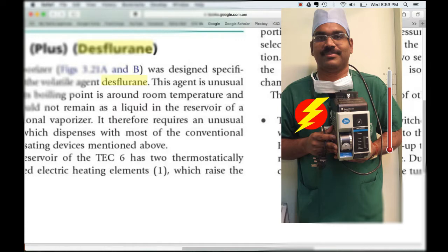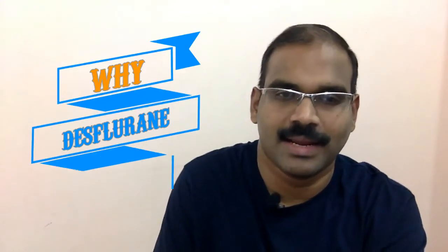Other contemporary volatile agents like halothane, isoflurane, and sevoflurane, with boiling points around 50 degrees Celsius, are vaporized using conventional flow-over vaporizers without supplying thermal energy. Hi, I'm Sanish, welcoming you to another edition of Tools in Anesthesia and Critical Care.